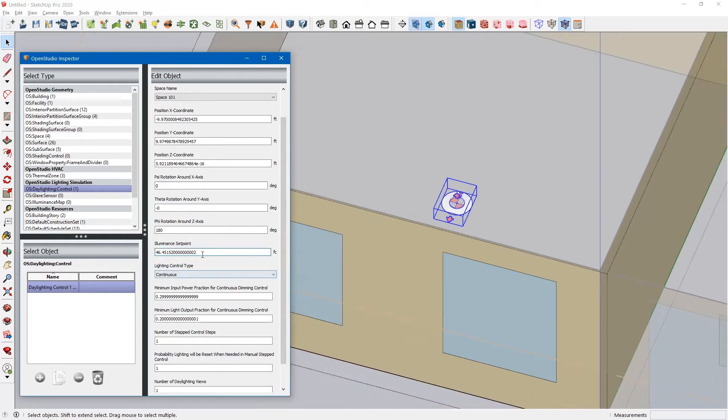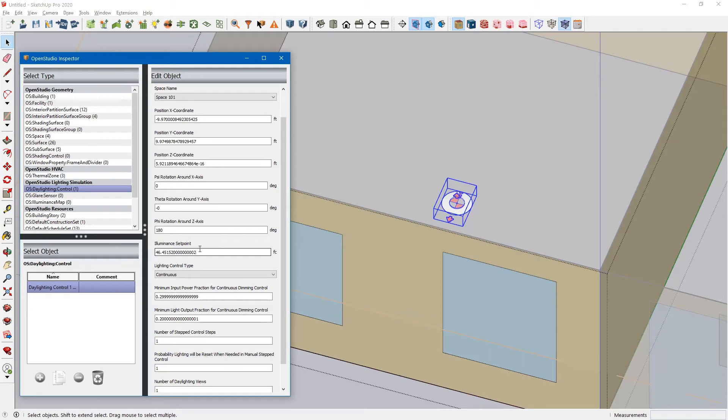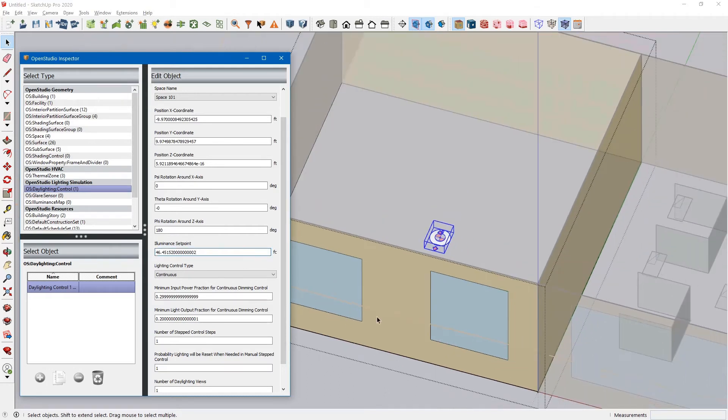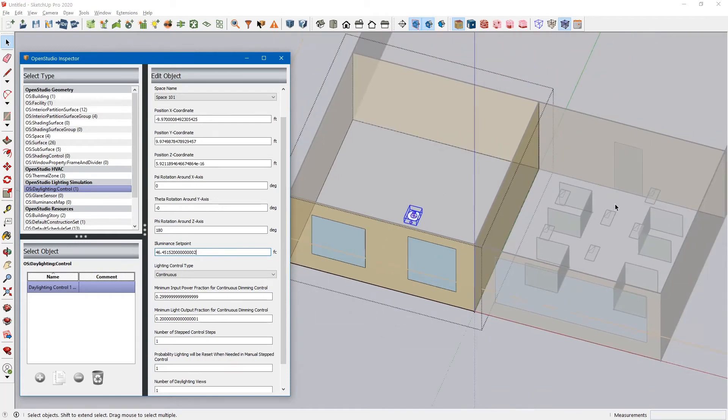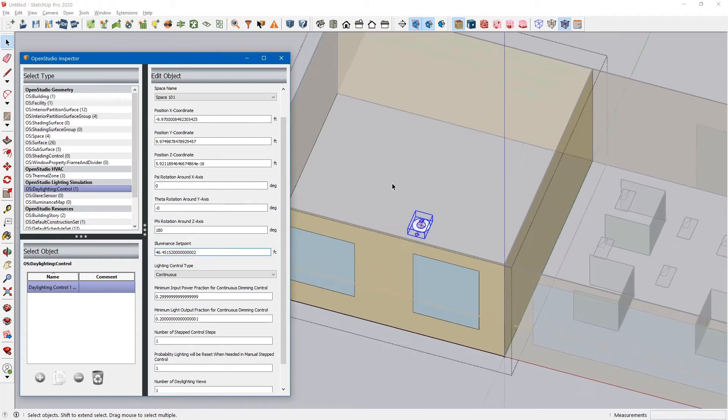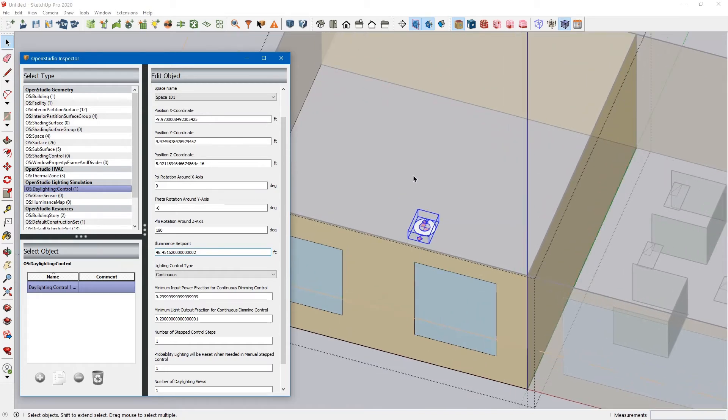This illuminance set point is the illuminance of the room in the middle of the night. Basically, when there is no sunlight coming through the window, it is the design illuminance of your lighting fixtures. You're going to want to know what that design illuminance of those lighting fixtures are, or at the very least, what the expected illuminance for this particular space type is.